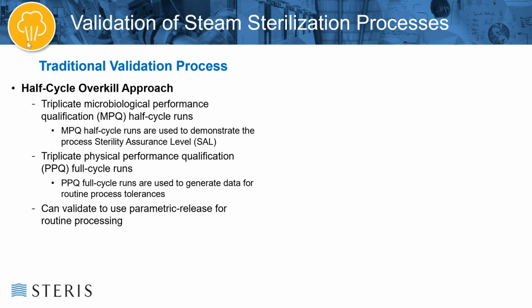Now, this triplicate MPQ and triplicate PPQ runs is operating under the assumption that you have a fixed load configuration. Oftentimes, we'll have products or customers that want a variable load configuration, so they want us to be able to send either 20 units or 200 units to be sterilized. They want that flexibility in their lot size. So when that happens, we actually want to execute 3 MPQ runs with the minimum load configuration, followed by 3 MPQ runs at the maximum load configuration, so that we're bracketing that variability and understanding that this process is effective with the minimum load as well as the maximum load. And then by extrapolation, we can say that anything in between those will also be effectively sterilized.